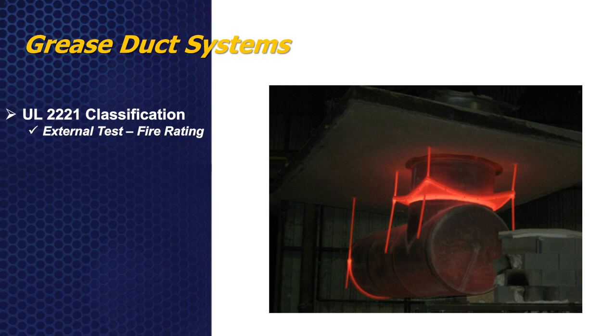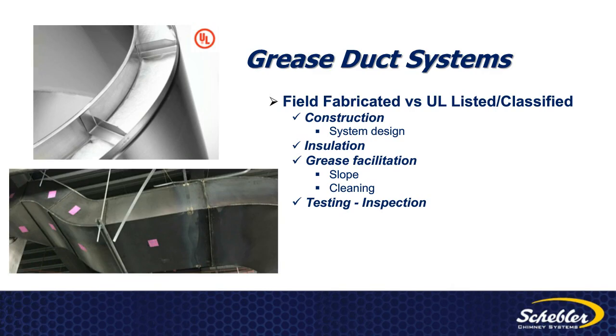So let's do a quick comparison of field fabricated grease duct versus UL listed and classified. We're going to look at the construction, the system design, the installation methods that are going to be utilized, the facilitation of grease if it does enter the ductwork, which we know it does at times, so we'll look at slope, cleaning methods, and then testing and inspection methods that will be done in the field to verify that it's installed properly.